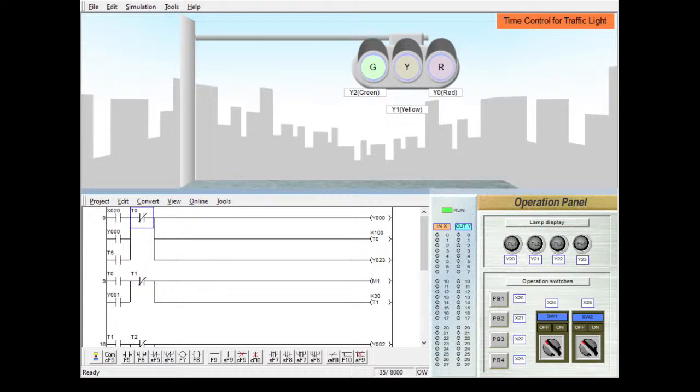Then the same timer puts on another section here. Then of course put on M1, set a timer. That timer puts off itself. Oh sorry, we didn't latch it here. That's one of the errors. So that's one of the ways of troubleshooting.